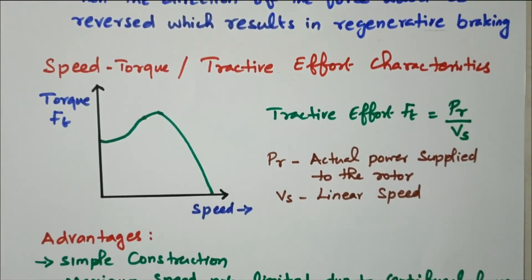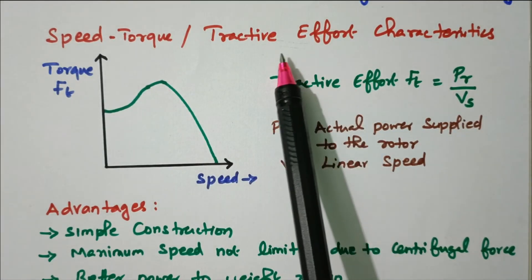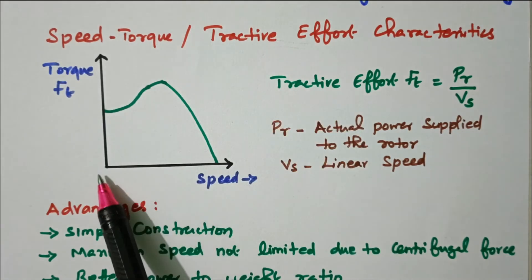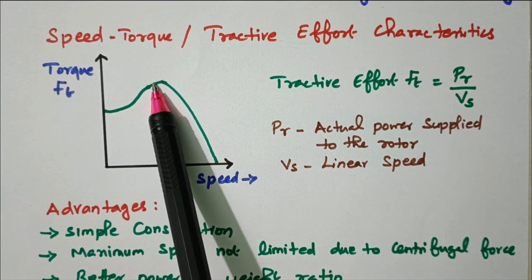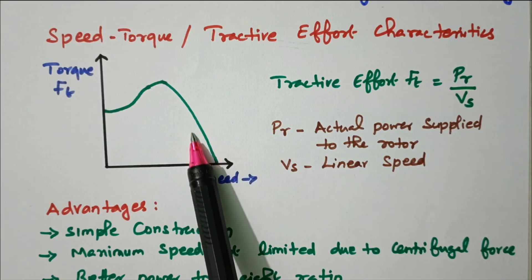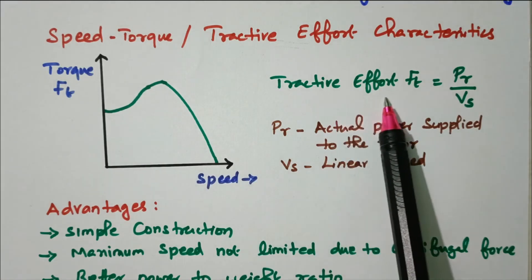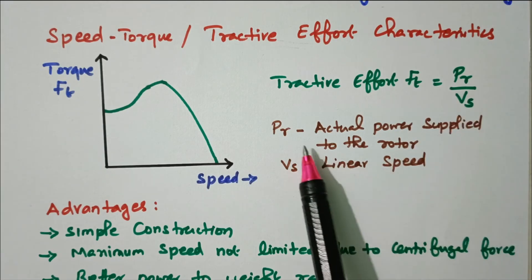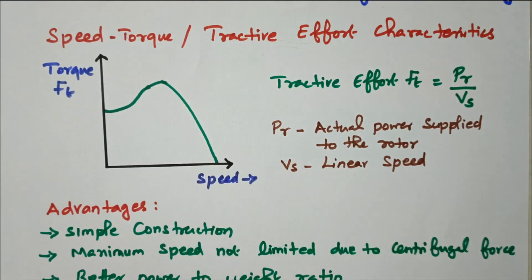Now we will see the speed-torque characteristics of the linear induction motor and the tractive effort. Speed is on the x-axis and torque on the y-axis. As speed gradually increases, the torque gradually increases to a maximum value and then becomes zero. The tractive effort Ft is given by Ft = PR / Vs, where Vs is the linear speed and PR is the actual power supplied to the rotor.